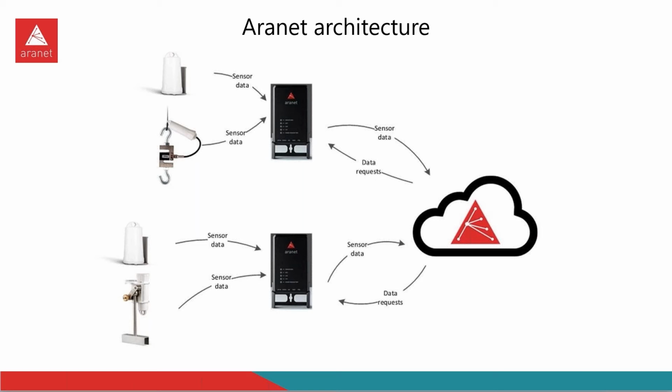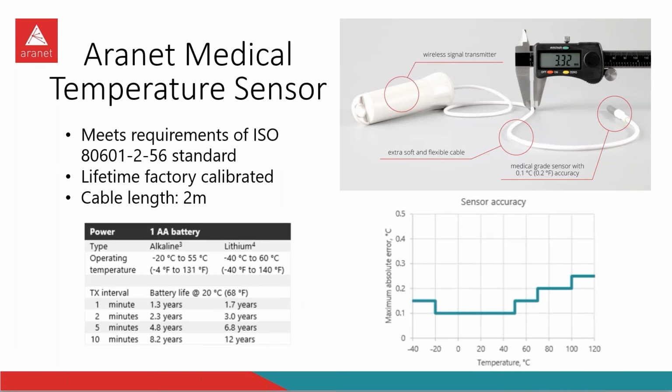The main sensor that is connected to our transmitter is our newest of the Aranet sensors, which is the Aranet medical temperature sensor. What is important to mention for the sensor? It does satisfy this specific medical ISO standard, meaning particular requirements for basic safety and essential performance of clinical thermometers for body temperature measurement.